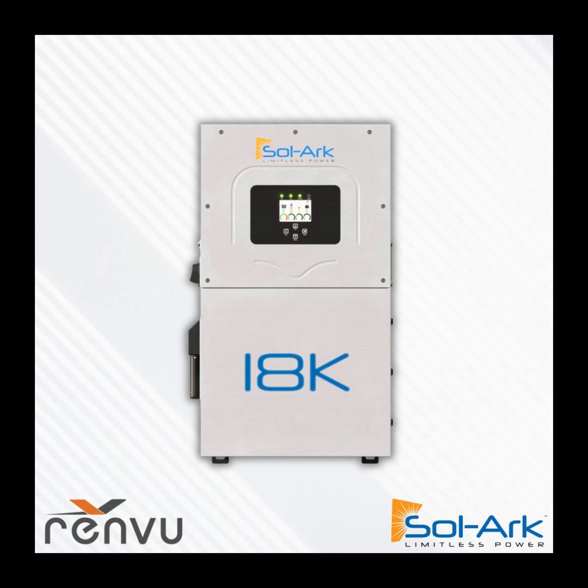But this is where I very much like the idea for commercial of, instead of doing whole building backup, doing distribution panel backup on a panel by panel basis, for two reasons. One, you're not selling whole building backup. You're selling economics and then value-adding essential backup, so it's not the same risk as whole building backup. It's an economics-forward project, but also, to accommodate that, a 7, 8 to 10 year payback provides backup power. An economic-only project typically needs a 3 or 4 year payback, so those are hard to do in the small to mid-sized commercial.